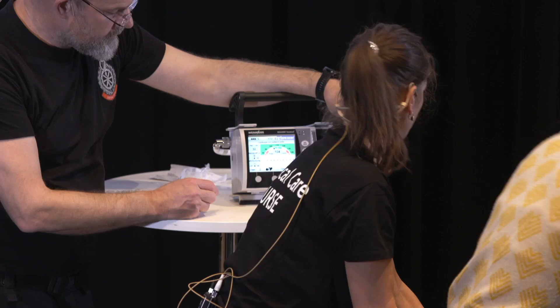Okay, we see positive pressure. So you're pushing in some air. And then recoil, because now we don't have the negative pressure, so the air is not going out. There's air going in, not going out. Your frequency is good, 100. There's still leakage on the patient side. Leave it. See, there's leakage going out. So, okay, we close it. Leakage gone. Okay, good. Okay, go on.